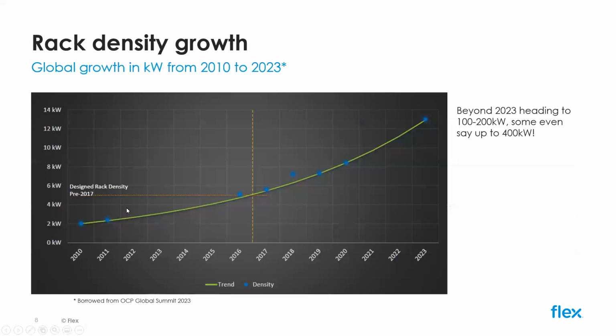If I rewind the tape and look 10 years back, we were talking about 2 kilowatts, 3 kilowatts, something in a rack in a typical data center. Today, we are looking more at 12 kilowatts, 14 kilowatts in most applications for data centers. But with AI, we have a projection to reach 100, 200, or even 400 kilowatts in a single rack. So you could imagine how much thermal challenges there are, how to dissipate this heat and manage these power levels in a rack. It is an extensive growth in kilowatts per rack.